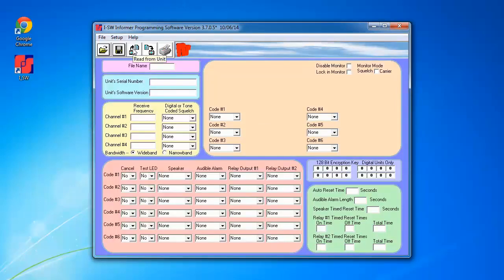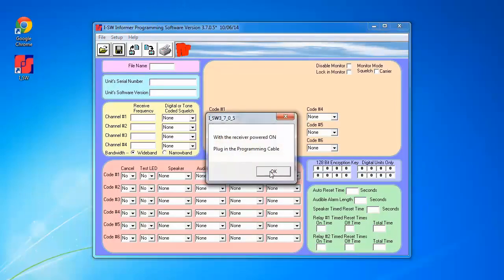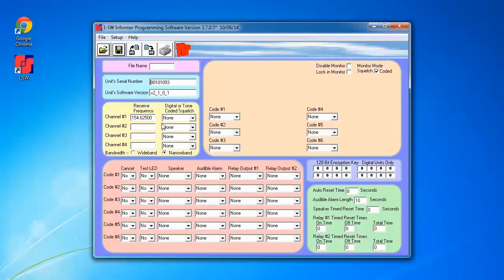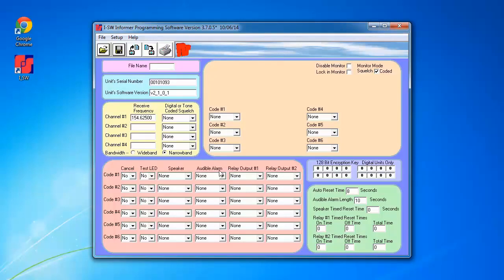Then we're going to read the programming out of the Informer. I'm going to click on the Read from Unit push button, click OK. It's going to briefly indicate that it's reading, and then the fields will populate according to what's currently programmed in the Informer. Right now, there's one frequency programmed in there, no codes and no audible alarms.